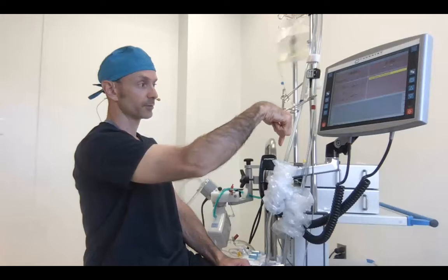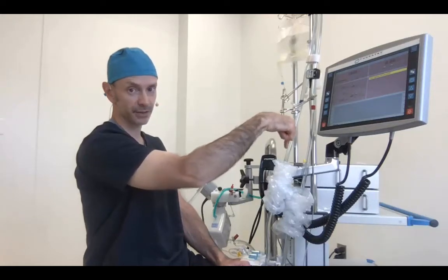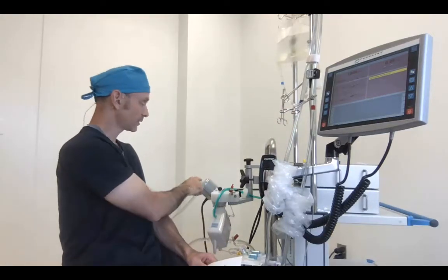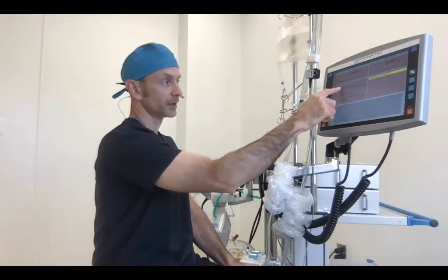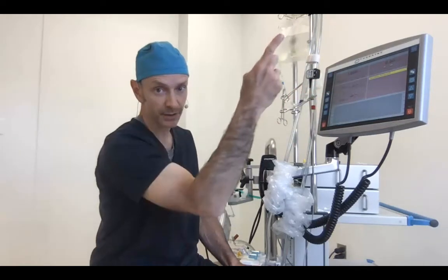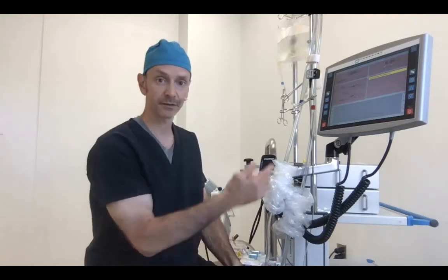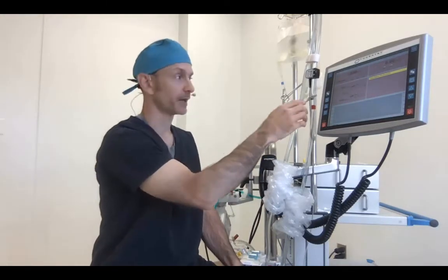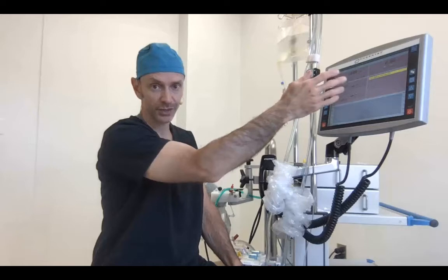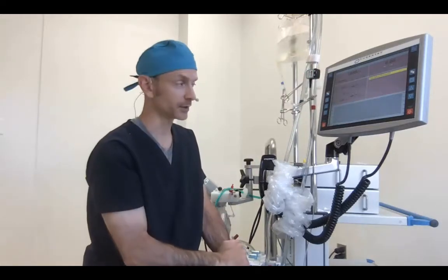Patient's over there, your pump is down here, your transducers are down here. And if you increase your RPMs until your line pressure is greater than what you're reading up there on the patient's hemodynamic monitor, then you'd be safe to take this clamp off. And if that happens at 1,000, great. If it happens at 1,400, then that's what you need, is 1,400.